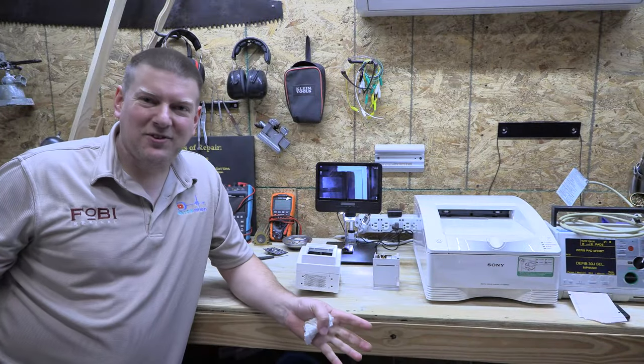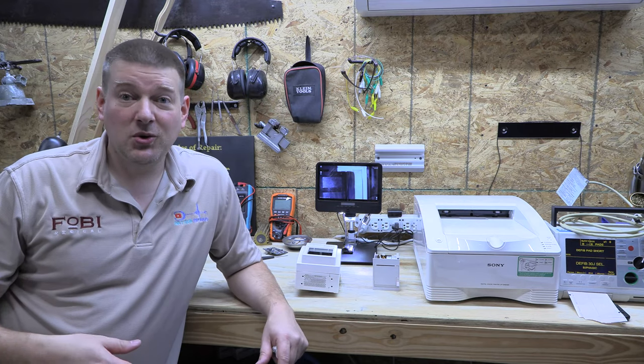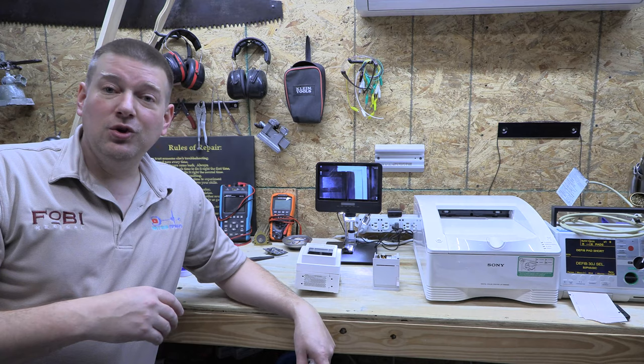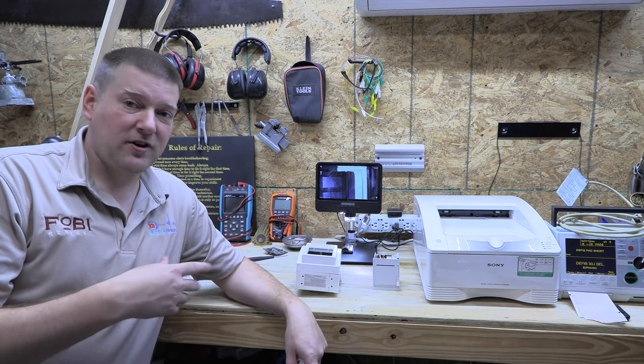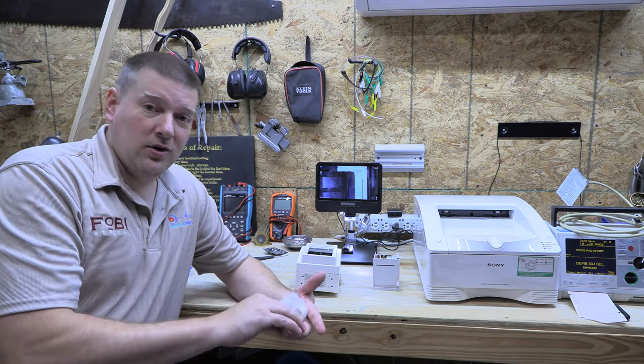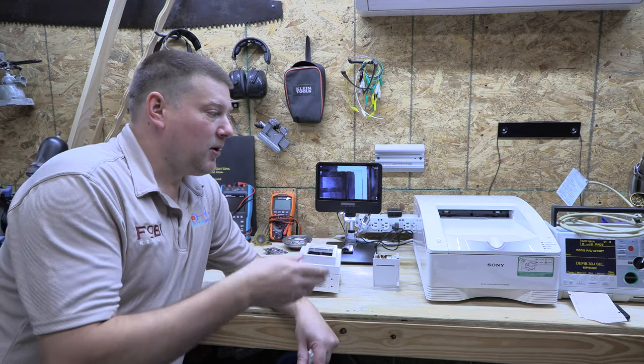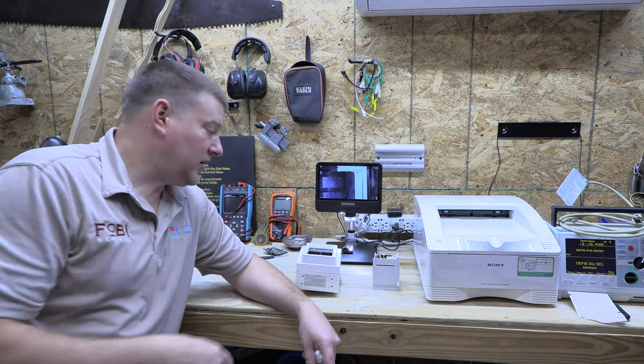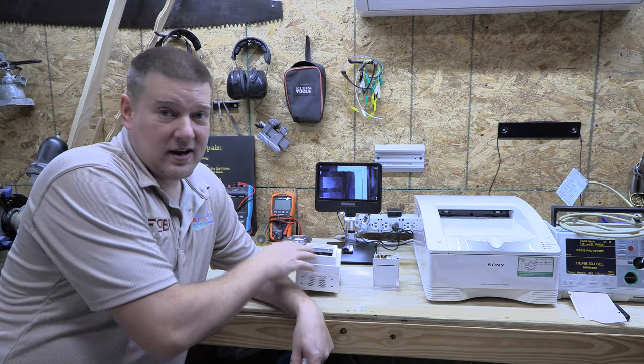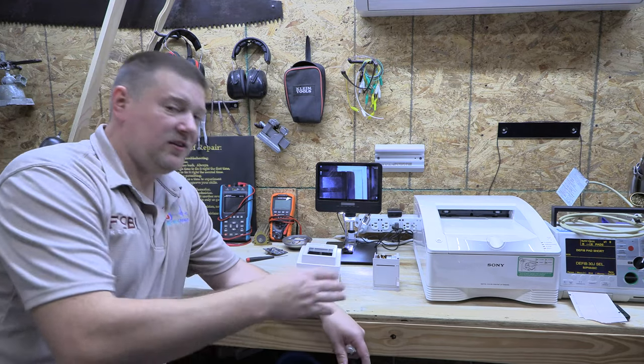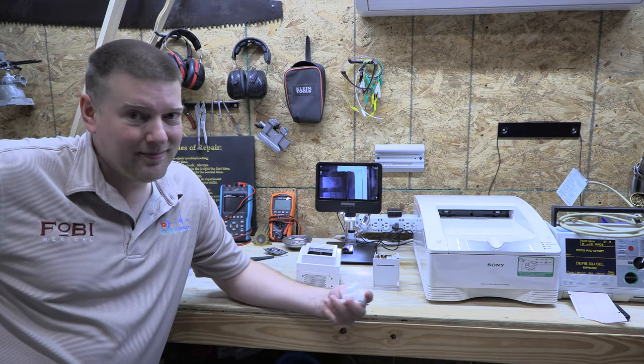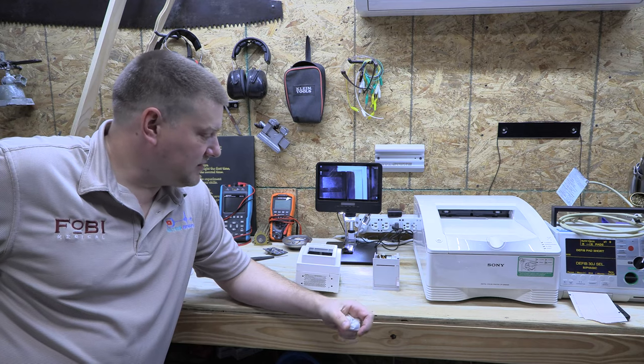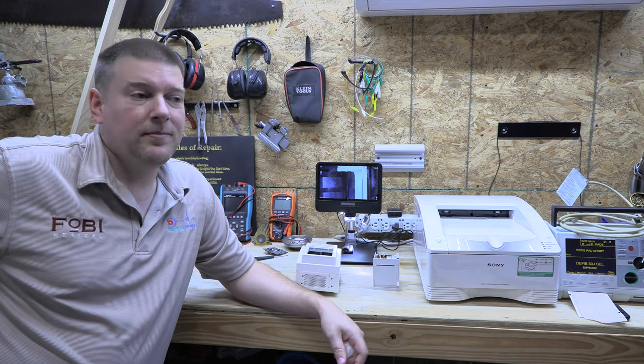So that is a transfer thermal printer. I figured this would be the excellent opportunity to whip out a few of my printers that I have laying around and show you guys how the technology works. You will be encountering these type of printers throughout medical facilities and professional office buildings. It's good that you know how they work and how you can maintain them if you need to. Some printers you have to change out the entire consumable and now you're back up and running. Other ones you might have to clean the print head and change the consumable. Things like humidity affect all printers equally, and things like wear and tear, obviously.